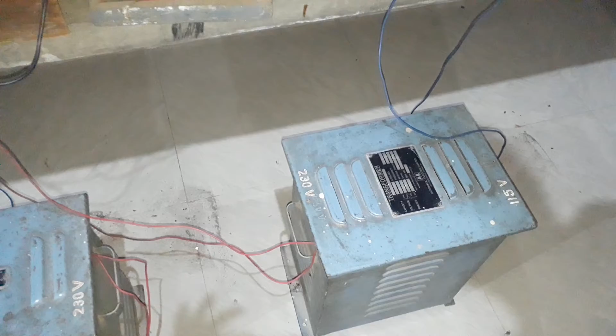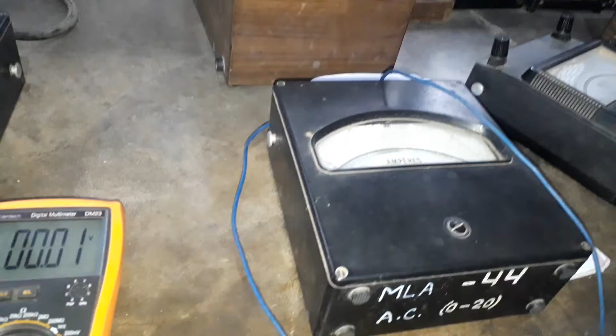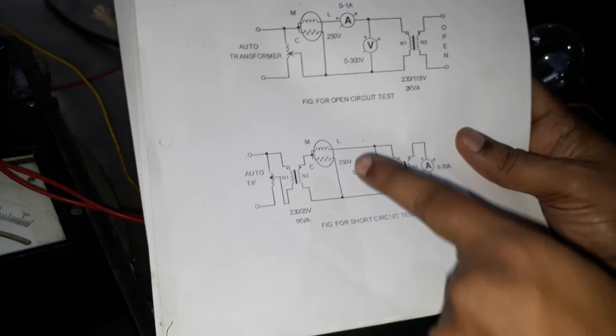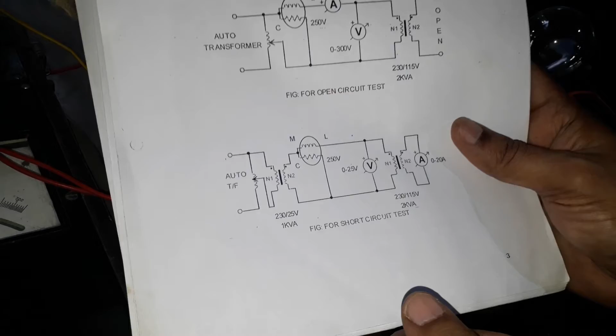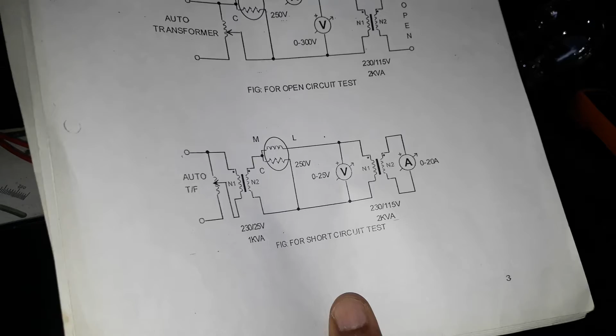In the same experiment, in the same setup, we also have to perform the short circuit test, which will follow. What we have done is, on the low voltage side, on the 115 volt side, we have short circuited this winding by connecting an ammeter between the two terminals of the LV side. On the HV side, again the equipments have been arranged exactly in the same manner as you see in your circuit diagram, but there is one important change: we have to replace the wattmeter which was used earlier with a different wattmeter of different rating, because now the transformer has been short circuited.